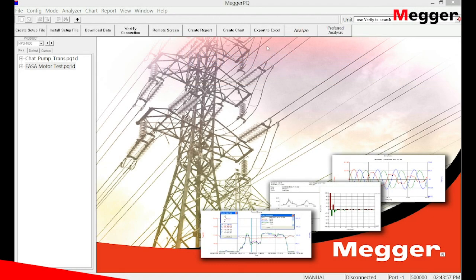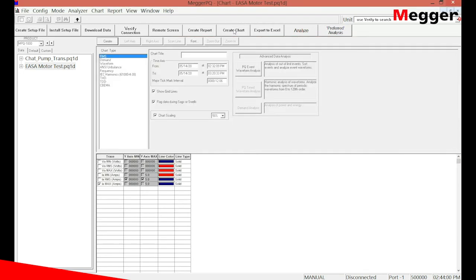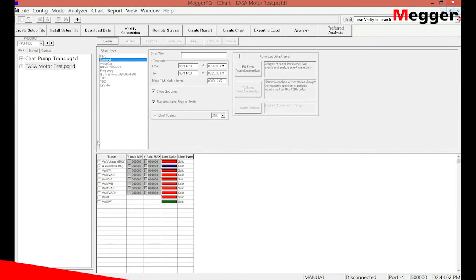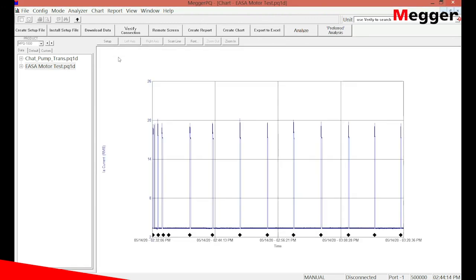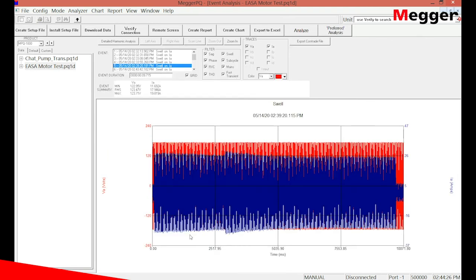So the data has now been transferred to the PC, and from here I can view the cycle-by-cycle voltage, current, kW, kVAR, kVA, as well as the power factor throughout the entire testing interval. But let's look at the cycle-by-cycle current inrush. We can clearly see the inrush from each motor turn-on. Each diamond is a link to the waveform that was captured for each inrush. Click on the diamond, and we can view the waveform for each inrush.